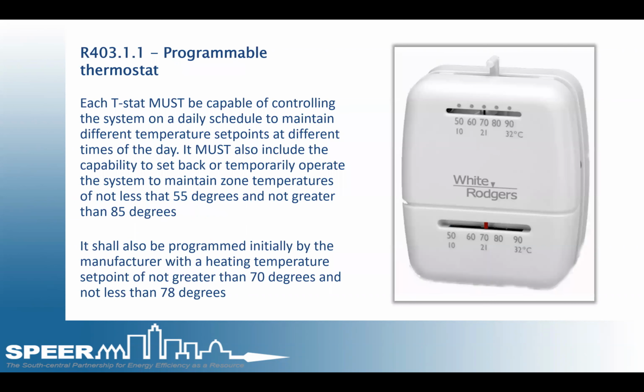403.1.1 programmable thermostats. So this is something I see a lot. If we read what it says here, it must be programmed, it must have setbacks, and it must not have a temperature lower than or greater than a set limit. But we see this a lot, where contractors are allowed to turn the AC units down into the 60s or less during the summer and into the 80s or higher in the winter. I know installing floor in the house needs the house to be warmed for installation, but most of the time it's just left at the higher setting.